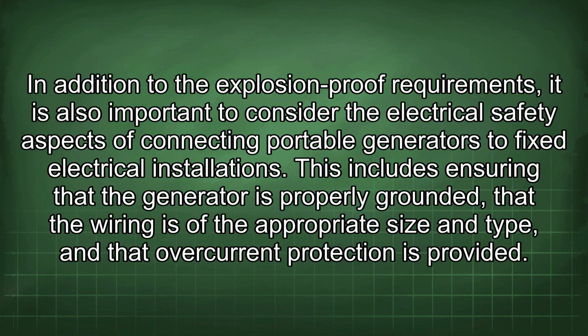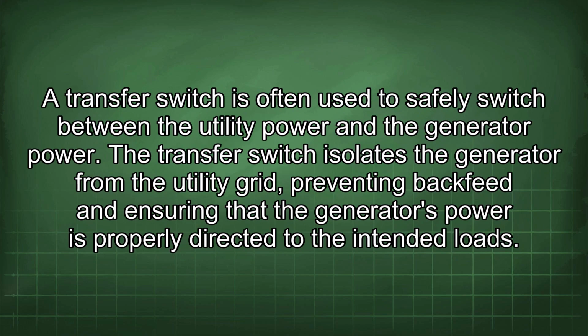In addition to the explosion-proof requirements, it is also important to consider the electrical safety aspects of connecting portable generators to fixed electrical installations. This includes ensuring that the generator is properly grounded, that the wiring is of the appropriate size and type, and that overcurrent protection is provided. A transfer switch is often used to safely switch between the utility power and the generator power. The transfer switch isolates the generator from the utility grid, preventing backfeed and ensuring that the generator's power is properly directed to the intended loads.